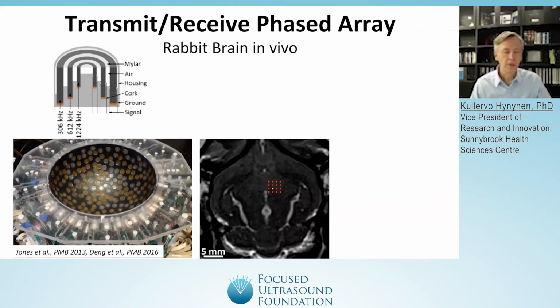So for the past 10 years or so, we have been developing different phased array transducers for testing different ideas for treating brain tumors and brain tissue. And this is one of the arrays, where we have three transmit-receive elements. So each of these could be used for transmitting or receiving. And typically what we do, we transmit at 600 kilohertz and listen at 300 kilohertz for the subharmonic, or 1.2 megahertz for the second harmonic. And these modules are distributed along a hemispherical surface based on a computer simulation optimized array design. It allows complete electronic steering of the beam.